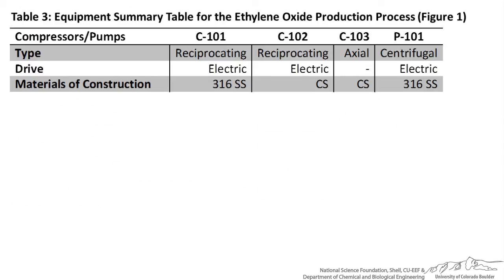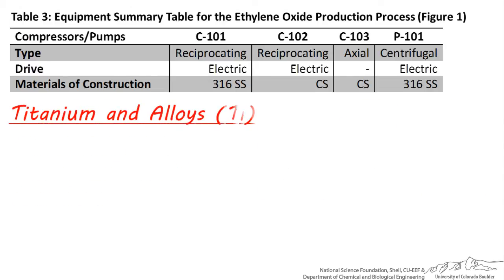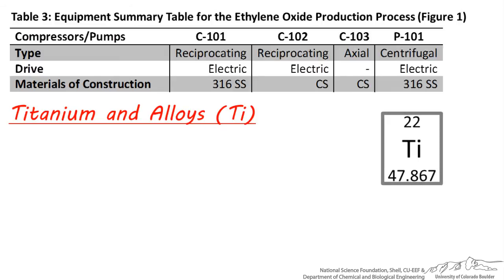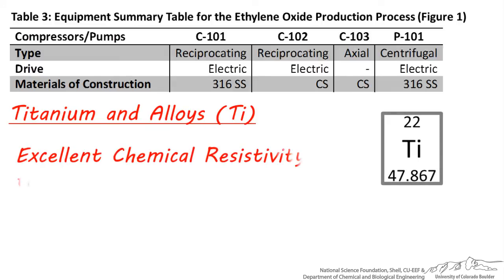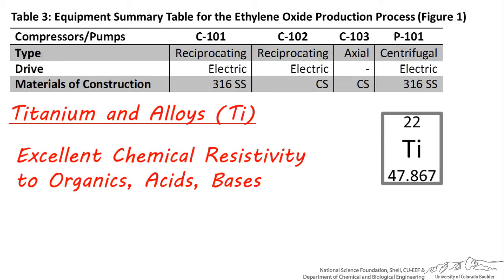Lastly, one of the most expensive materials you can select is Titanium, abbreviated Ti. Its alloys are lightweight and safe to use for almost all organics, acids, and bases, except chemicals like hydrofluoric acid or concentrated sulfuric acid.